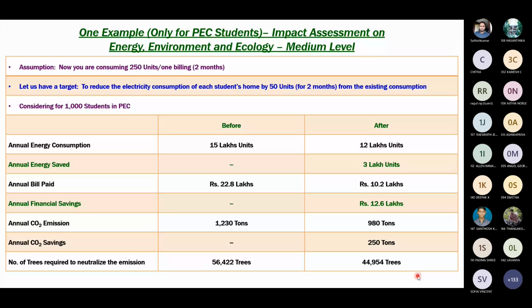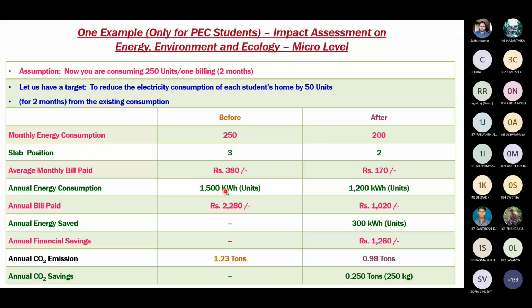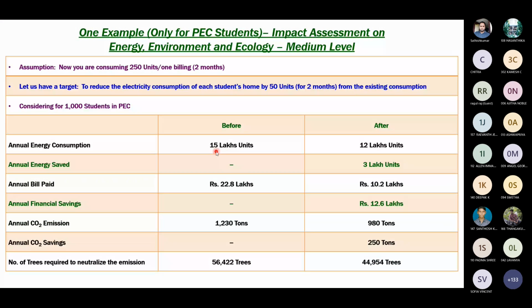Now everything is multiplied by 1,000. Earlier consumption of 1,500 kilowatt hour becomes 15 lakh units, now reduced to 12 lakh units, a saving of 3 lakh units instead of 300. The bill goes from 22.8 lakh to 10.2 lakh, a saving of 12.6 lakh rupees.